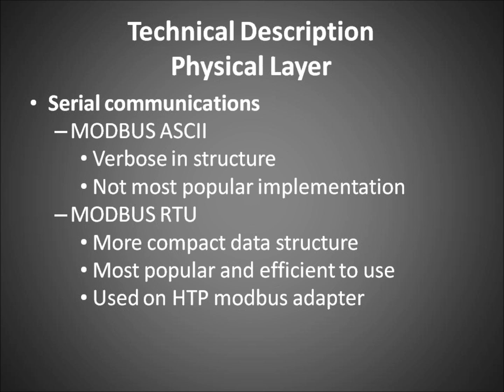There are different ways to frame the data that's transmitted and received. One is called ModBus ASCII and one is called ModBus RTU. By far the most popular method in use is ModBus RTU because you can send less data to transmit the same information, so it's a more efficient use of the communications, and that's the one we use in our product. In ModBus ASCII, you have to send more digital data over the bus to transmit the same information, so it's not as popular. So there's more overhead in the communications. Right. Okay, all right, thank you.